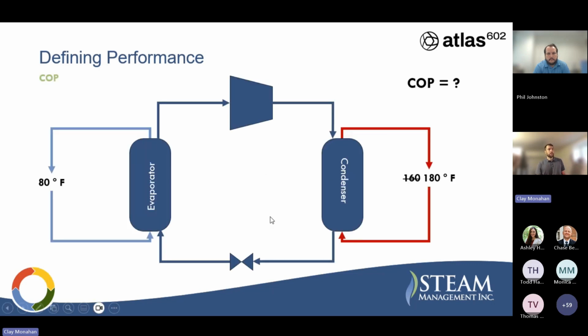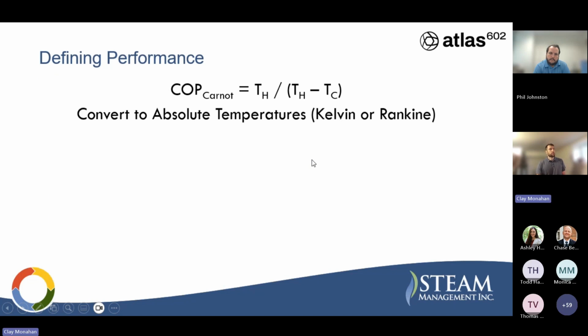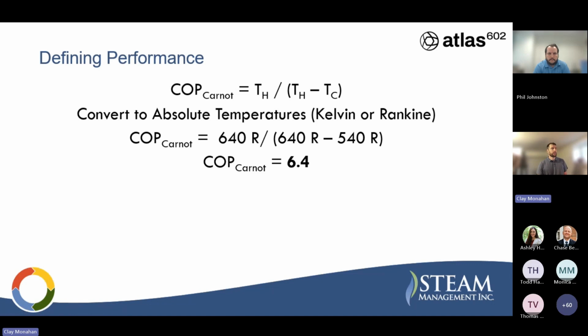So going back to our slide, if instead of a 160 degree heat sink we have a 180 degree heat sink, we have a higher lift across our heat pump. Now we're up to 100 degrees Fahrenheit instead of that 80 degree mark. Let's figure out our new COP. Same thing, using our formula and converting to the absolute temperatures, but now having that higher lift, we see a drop in the COP to 6.4. So higher lift across the heat pump is going to lower our COP.